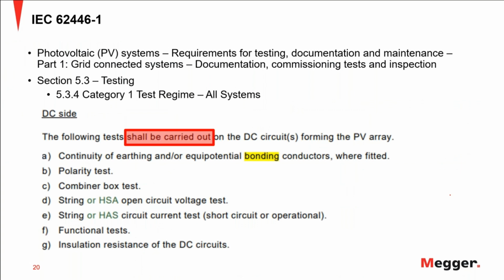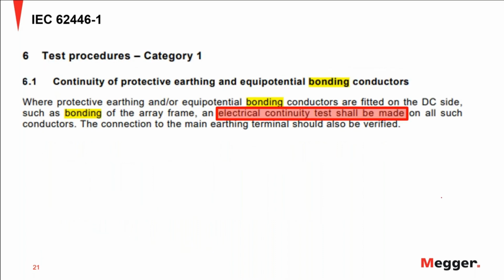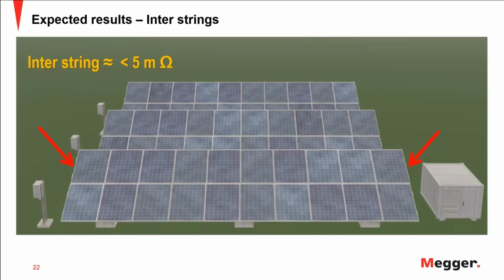IEC, again, is not that common here in the US, but this standard for photovoltaic systems also shows that the tests shall be carried out, and one of those tests is the bonding of the conductor. So you need to test those according to this standard as well. If you want, you can receive the slides, and you're going to see all of these details in the slides. So how to perform the test? Here we have a typical depiction of a solar array.